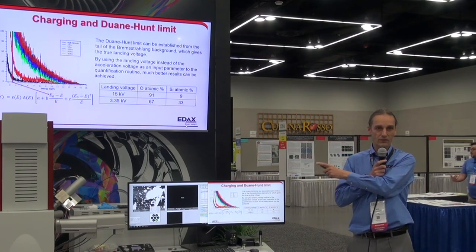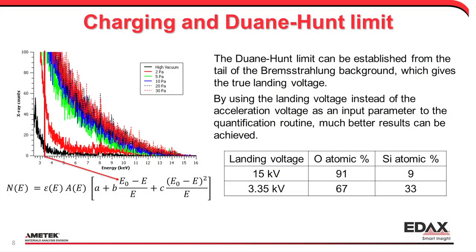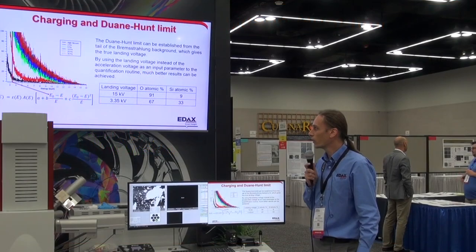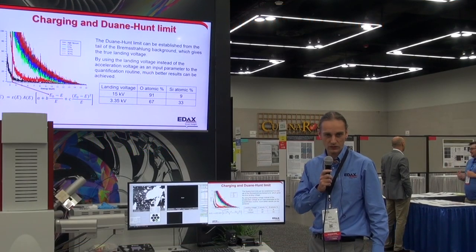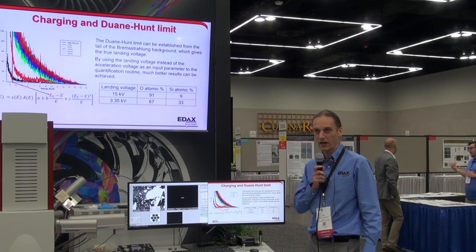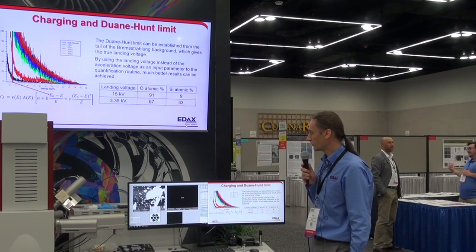If I tell our quantification model that I don't have 15 kilovolts but 3.35 kilovolts — because as we can see from the spectrum that's the Duane-Hunt limit — all of a sudden I get reasonable quant numbers: silicon dioxide at 66/33. So 3.35 kilovolts is around where my actual landing voltage is, not the 15 we thought we had based on the acceleration voltage. And you can easily see this just by looking at the tail of the background.